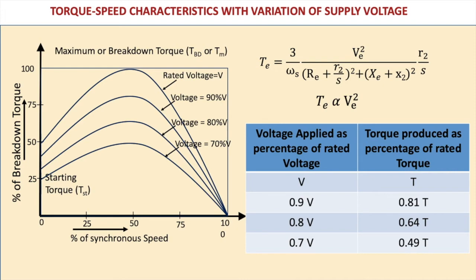So if the starting torque is less than the load torque which is connected to the motor, the motor will fail to start. So this is how we try to calculate the value of the X in the auto transformer, that is, what should be the minimum torque, and according to that, what should be the minimum supply with which we can start the motor.